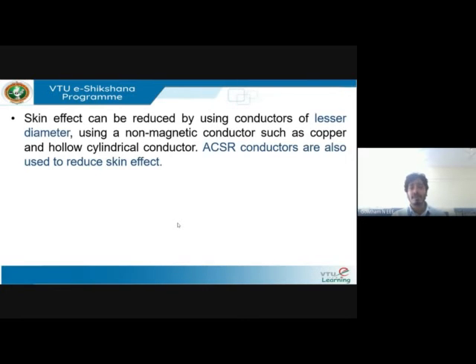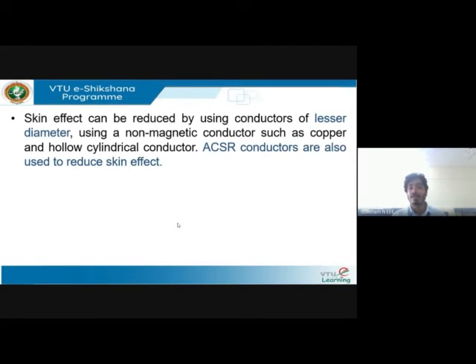To reduce skin effect, ACSR conductors — aluminum conductors steel reinforced — are usually recommended. They are recommended both to reduce sag and to reduce skin effect. Using a material with a smaller diameter and a non-magnetic conductor like copper also helps reduce skin effect, since magnetic materials have higher permeability, which increases skin effect according to the delta expression. Preferably using ACSR conductors reduces skin effect since solid conductors experience it more.